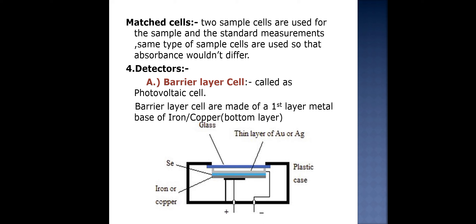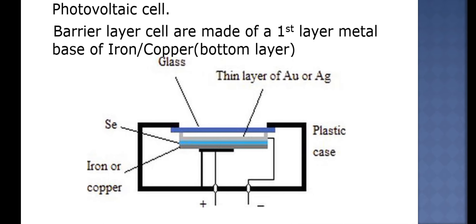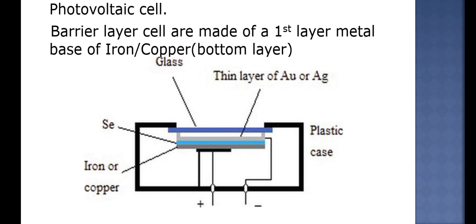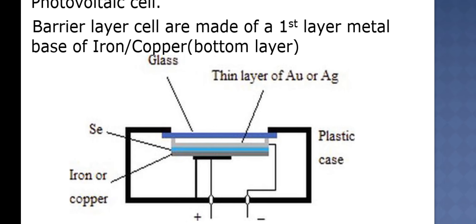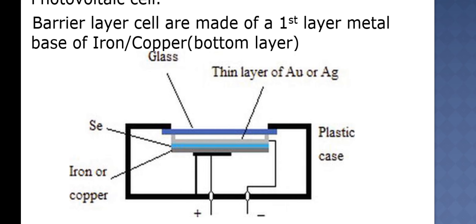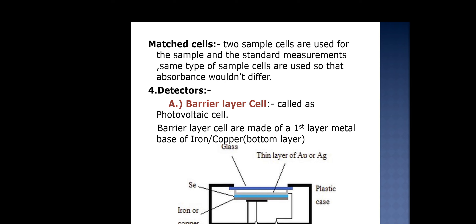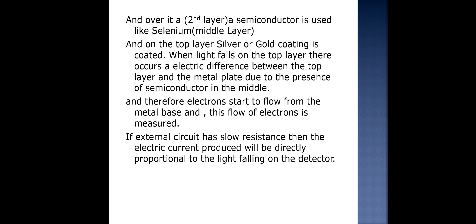The fourth instrument is the detector. The first type is the barrier layer cell, also called the photovoltaic cell, which has three layers. The topmost layer consists of silver or gold plating, under which a selenium semiconductor is coated, and the bottom layer consists of iron or copper as a metal base. This layer is connected with the circuit. When light falls on the topmost silver or gold layer, a conductivity difference — or electrical difference — occurs between the top and bottom layers. Due to this, electrons flow from the iron or copper layer towards the circuit, and these electrons are measured. If the external circuit has low resistance, the electrical current produced will be directly proportional to the amount of light falling on the detector.